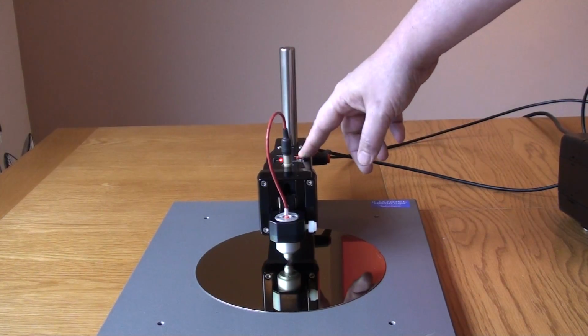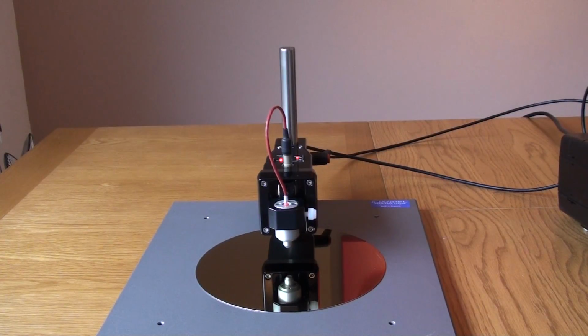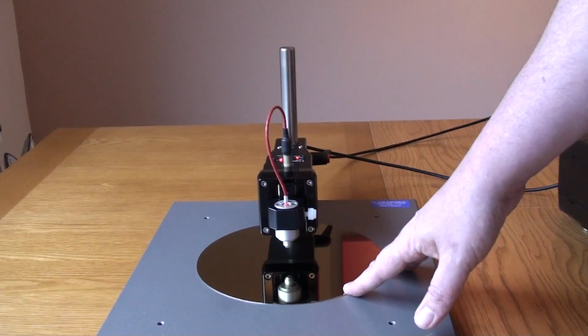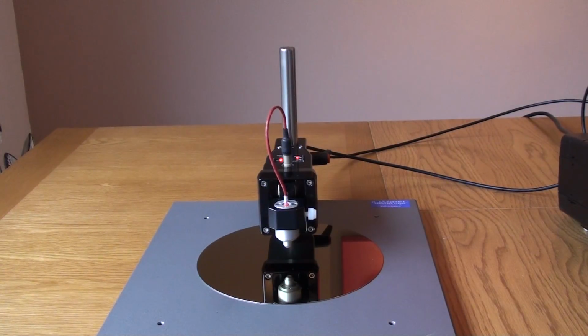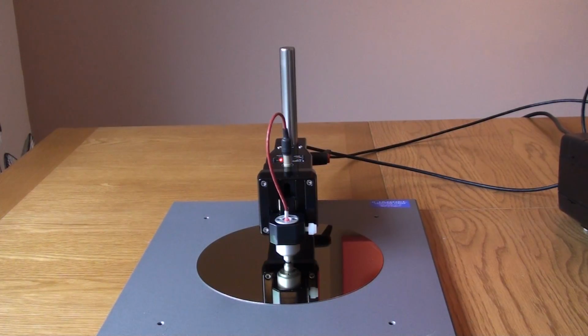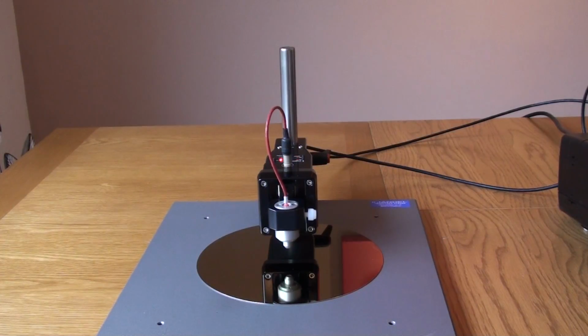Pressing the home button raises the probe head. If you are using the RM3000 Plus, then by using a current and pressing the forward button, the probe will automatically lower onto the sample and a measurement will be made. Reverse readings at this point can also be made, and when standby is pressed, the probe will raise off the sample.